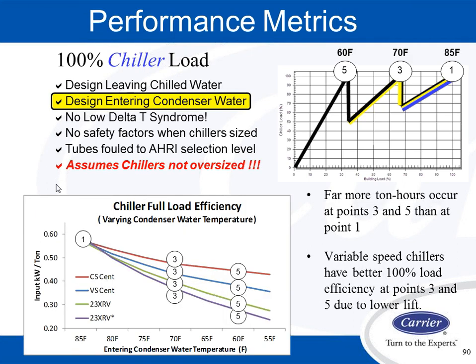So when we look at the points 1, 3, and 5, those are the 100% load point. Oftentimes there's a manufacturer out there saying, we had 30% of the hours in the 100% load point, that's why VFDs don't make sense. Well, if you look at that, they do operate at 100% load point, but they operate with cold condenser water. Because they operate with cold condenser water, we have the ability with the VFD to reduce the lift in the machine, centrifugal or screw. So that's why VFDs make sense at 100% load point.